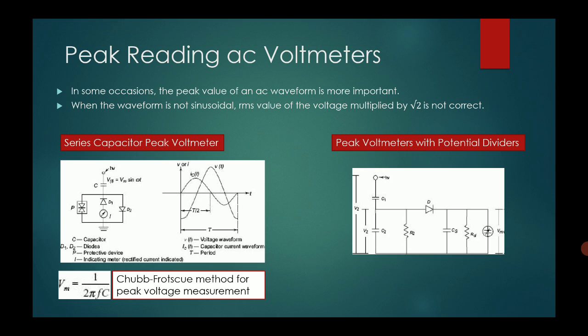Okay. Now we'll talk about peak reading AC voltmeters. These voltmeters read the peak value of the AC rather than the RMS value. On some occasions the peak value of the AC waveform is more important than the RMS value. When the waveform is not sinusoidal, the RMS value of the voltage multiplied by root 2 is not correct. You might say that if you multiply the RMS value by root 2, you can get the peak value, but that is only applicable for sinusoidal voltages. For non-sinusoidal voltages, such a simple method will not work.